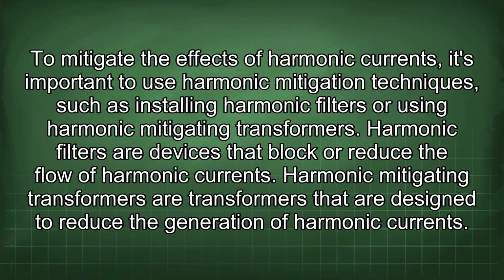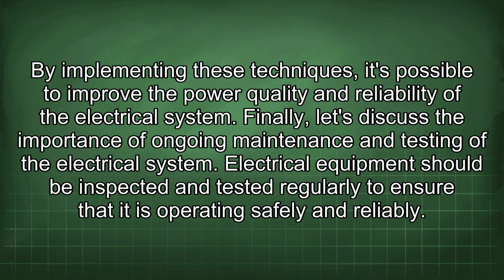To mitigate the effects of harmonic currents, it's important to use harmonic mitigation techniques, such as installing harmonic filters or using harmonic mitigating transformers. Harmonic filters are devices that block or reduce the flow of harmonic currents. Harmonic mitigating transformers are transformers that are designed to reduce the generation of harmonic currents. By implementing these techniques, it's possible to improve the power quality and reliability of the electrical system.